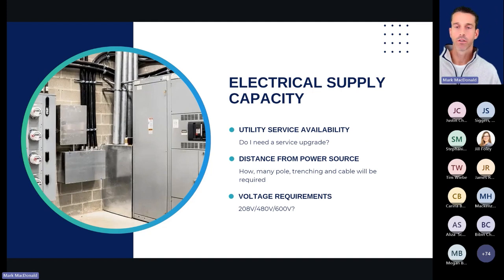This one's a no-brainer, pretty straightforward. Electrical supply capacity is one. Utility service availability - do I need a service upgrade? What's going to be my cost? Do I have enough existing kVA on that transformer or room in that switchgear to support the deployment of a 60, a 120, a 180, maybe multiple ports? That's going to keep your costs down and also keep your ROI a whole lot shorter.